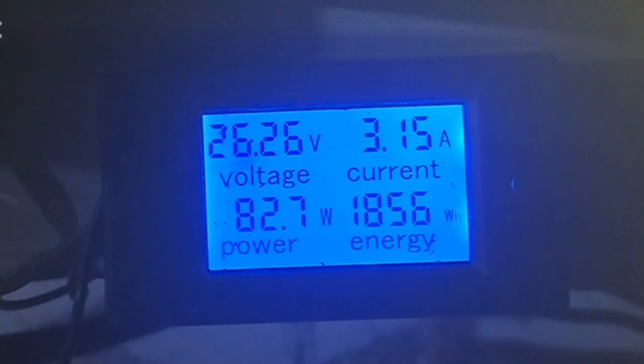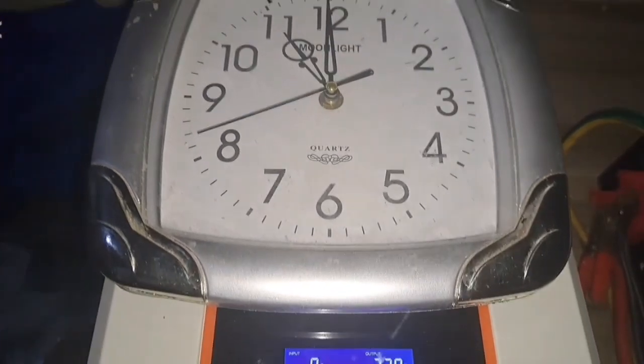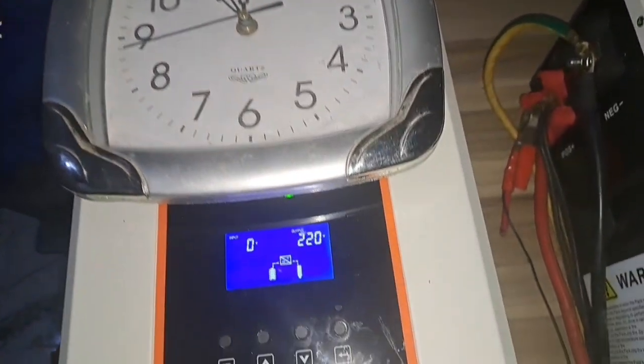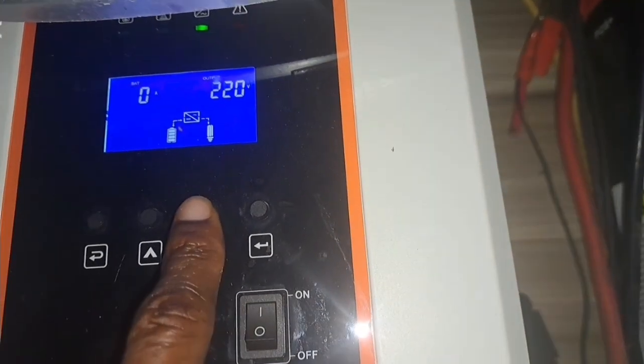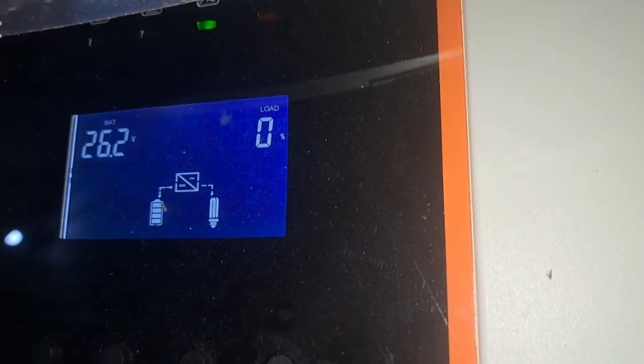And the key thing to note is this: if your inverter is serving you well, you just need to increase your batteries, unless of course maybe the charging current in the 3.5 kVA is much more when you're increasing your batteries. But you don't need to necessarily increase your inverter size. You just increase your batteries and you leave your inverter if it is working well for you.